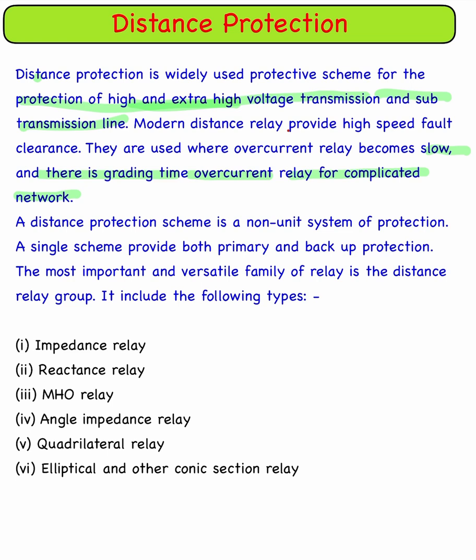A distance protection scheme is a non-unit system of protection, and a single scheme provides both primary and backup protection. The most important and versatile family of relays is the distance relay group. The different types of distance relays include: impedance relay, reactance relay, mho relay, angle impedance relay, quadrilateral relay, and elliptical and other conic section relays. We will discuss each one by one.